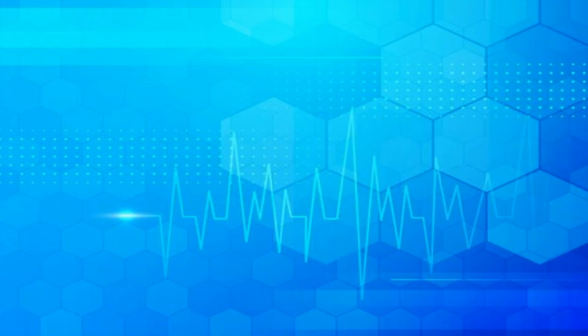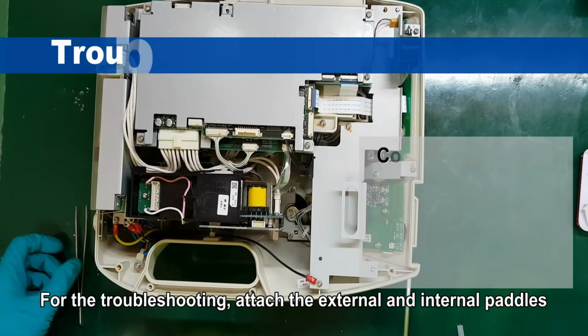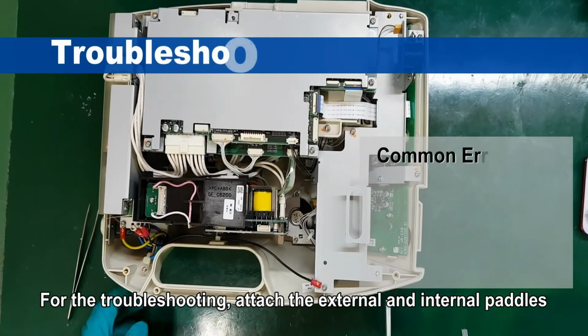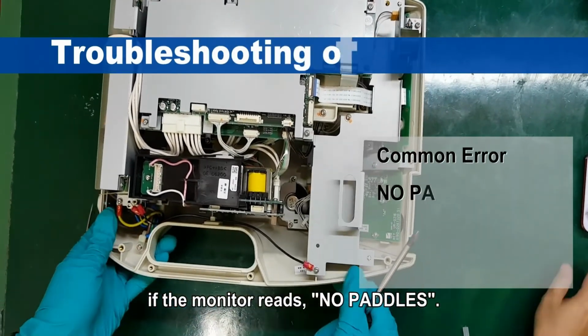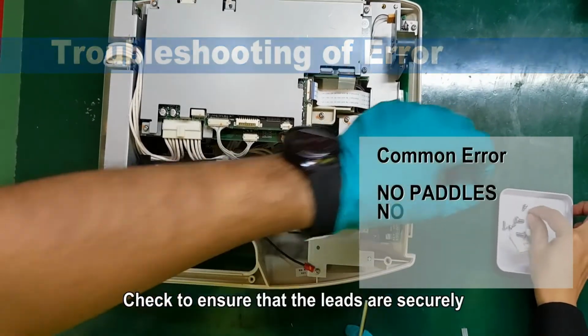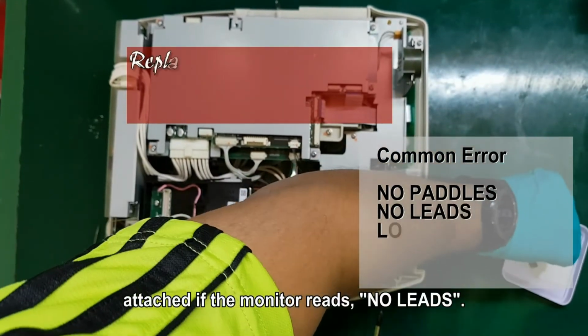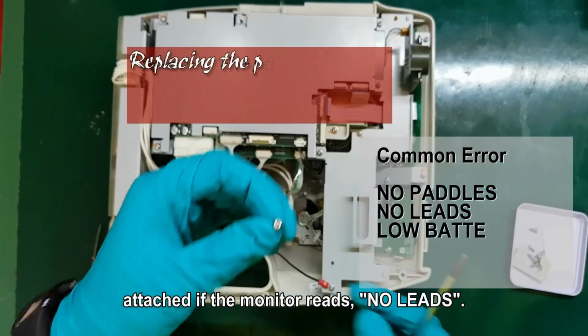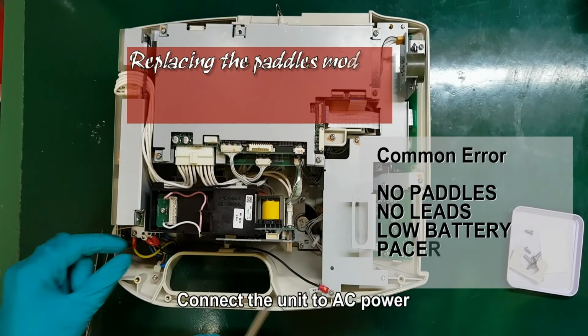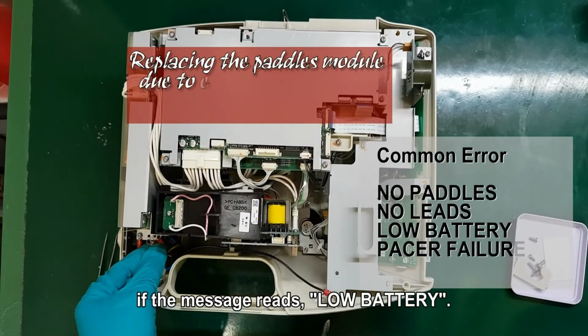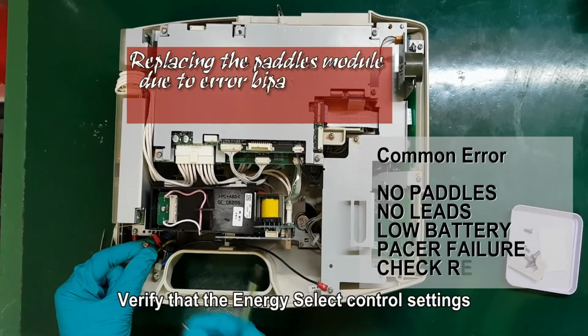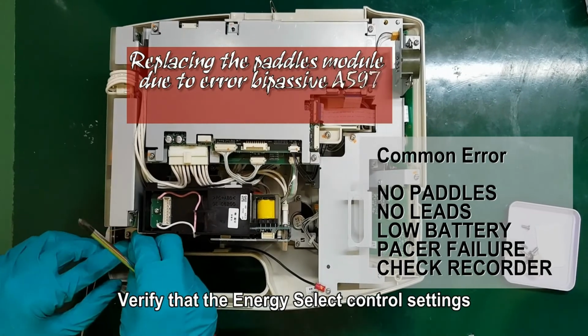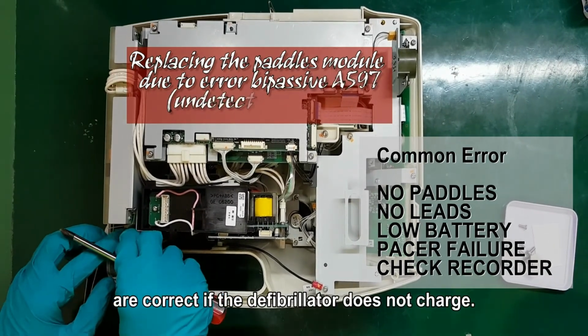Troubleshooting. For the troubleshooting, attach the external and internal paddles. If the monitor reads no paddles, check to ensure that the leads are securely attached. If the monitor reads no leads, connect the unit to AC power if the message reads low battery. Verify the energy select control settings are correct if the defibrillator does not charge.